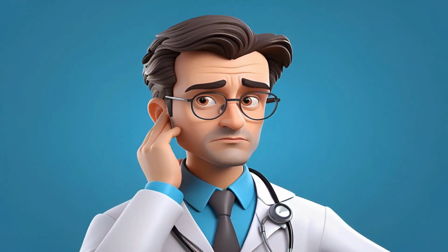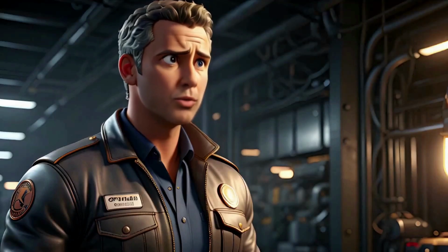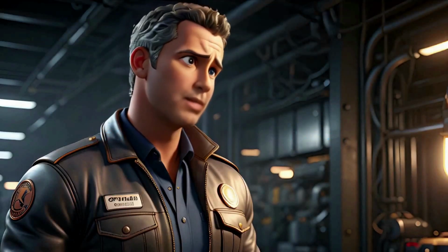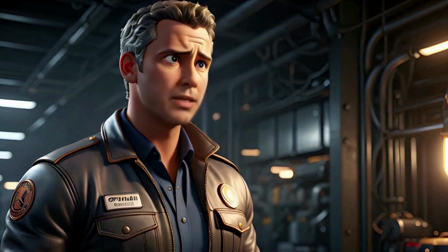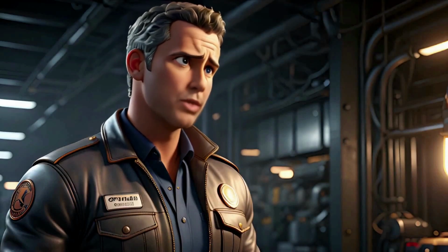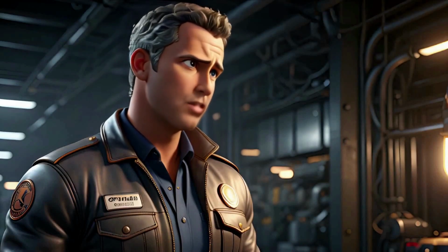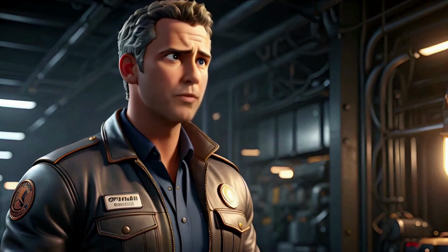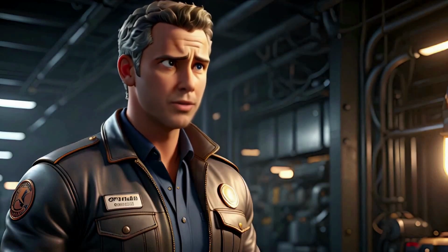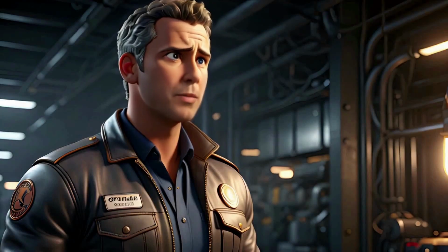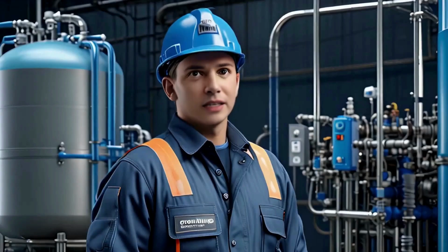What's the importance of scale control? If you control scale, you will increase operational efficiency. For example, scale reduces heat exchange efficiency, which increases operational costs and reduces the performance of cooling systems, boilers, and other water-based systems. Second is extended equipment lifespan: preventing scale buildup reduces wear and tear on industrial equipment such as pumps, pipes, and heat exchangers.